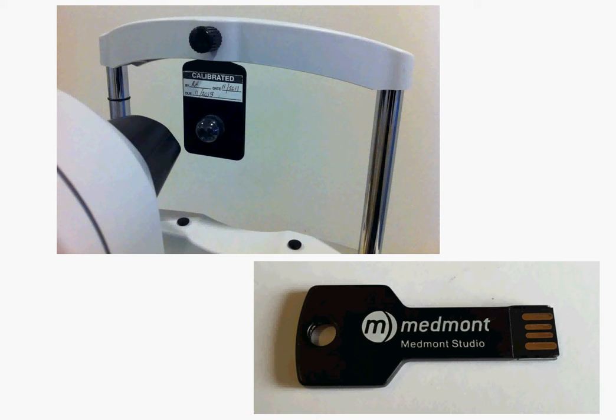Again, if this is the first time that you've done a calibration, you'll need the USB key with the calibration file specific to your Medmont on it. Simply insert it into the USB port and wait for the software wizard to prompt you to browse to that port. If you've done a calibration on your Medmont before, the USB file is already loaded and the USB key will not be necessary.